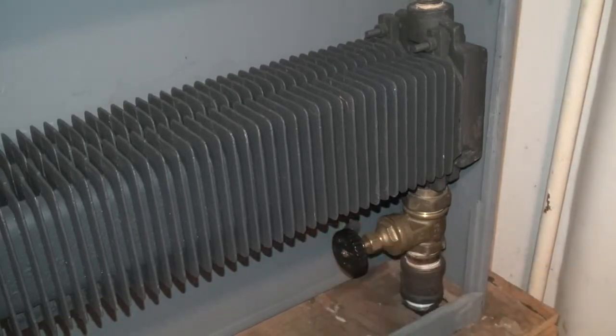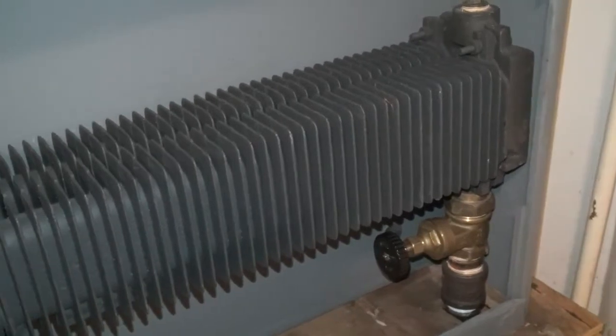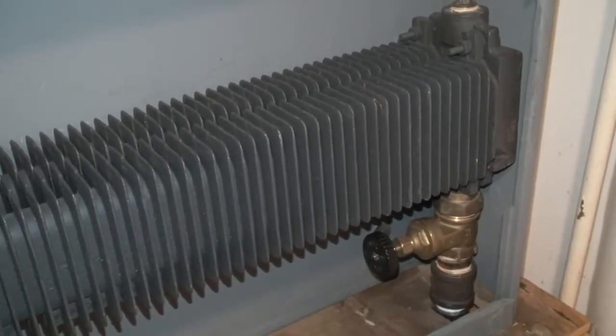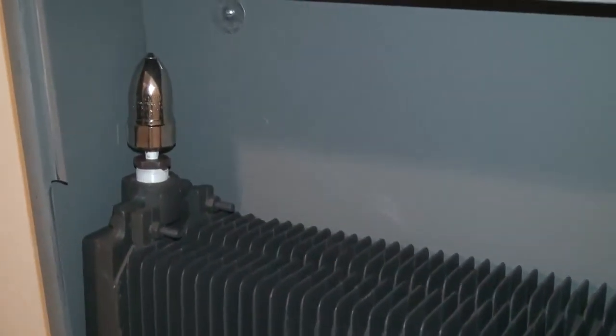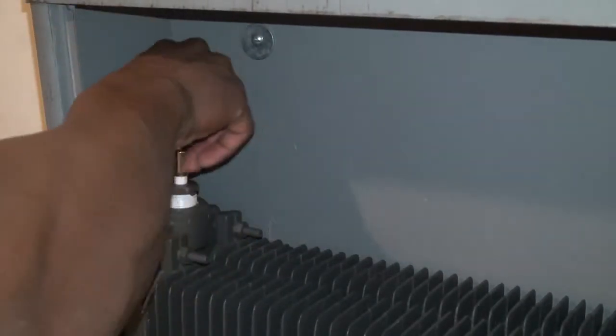Well, not from scratch. What I'm gonna do is have this build up pressure. I'm gonna let the system run because the thermostat is actually calling off the heat. I'm gonna gag this, put a plug inside of this air valve, and remove this. Now, of course, I'm probably gonna need some gloves for this. This thing is hot as hell, but of course I know how to work it just a bit where I don't get burnt.